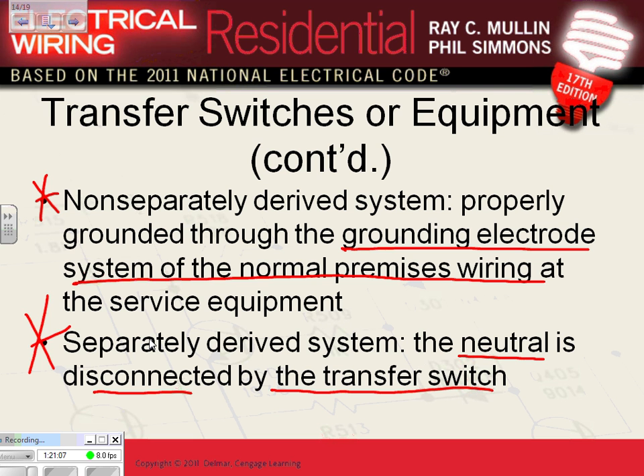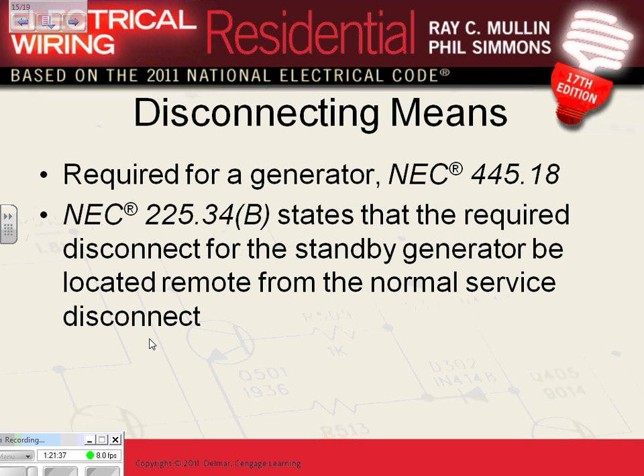Which system should I use? You can use any one of them, as long as you remember: if you're running nonseparately derived system, the neutral cannot be switched. If you're running a separately derived system, you have to switch your neutral. If you're plugged in, you have to run separately derived system. You have to switch your neutral, the portable ones, no option. For the little ones, the portable ones, you have to switch the neutral, no option. For the permanently mounted ones, you have the option.